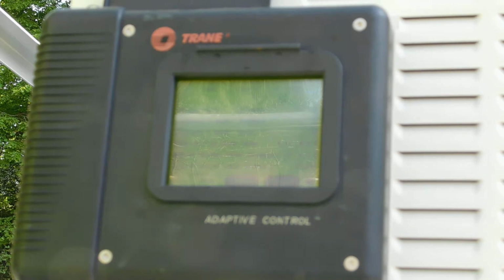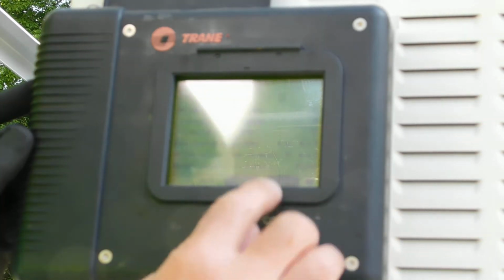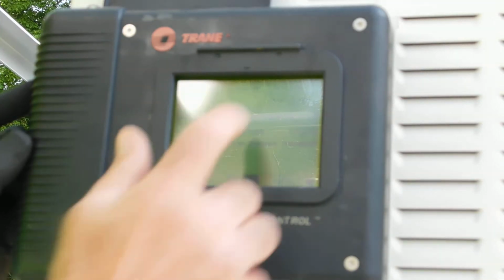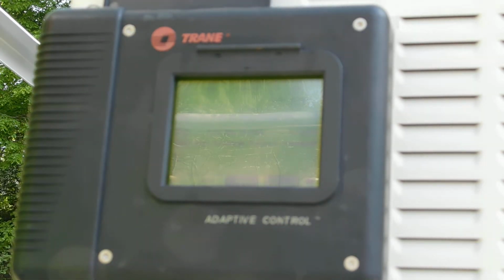So what I've just done is I've took off the connection to the discharge pressure transducer. So now it can't see any discharge pressure. If I press the alarm button, it literally tells you comms loss, discharge pressure transducer. I can reset that, but the reason it won't reset is because I haven't plugged it back in. If I now go and plug it back in, we can then reset it.